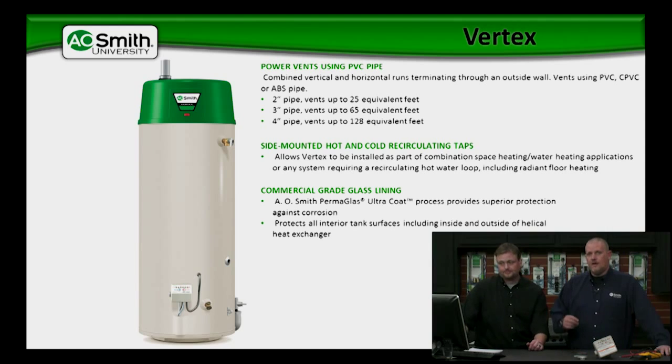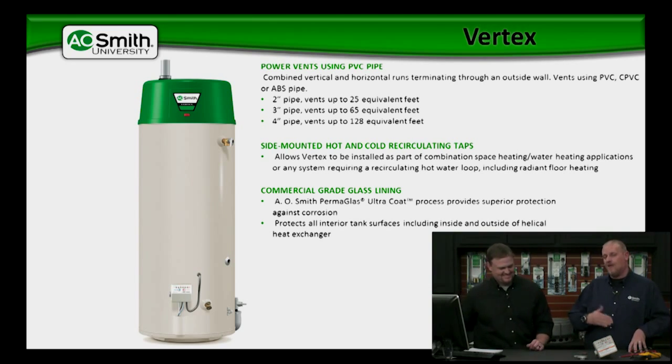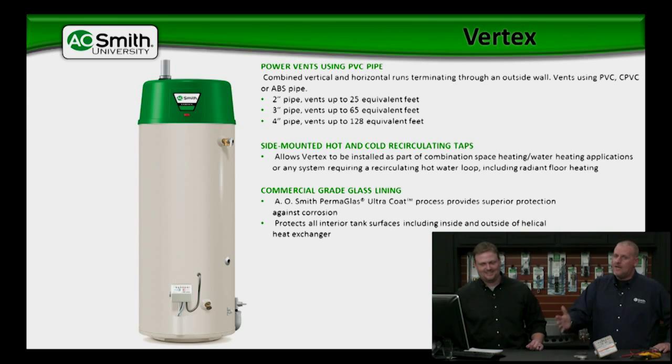What we mean by commercial-grade glass lining process is it means that all of the welding to the steel is done before the glass lining process. We build the entire tank, dunk it in the slip solution, and then run it through the furnace after all of the welding is done — after the welding. That's why we're not doing any seam welding after the glass lining process. It's just added protection.